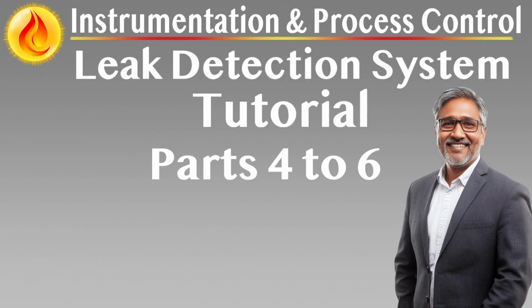These techniques are often used to supplement flow or pressure balance methods, providing an additional layer of detection that focuses on the leak's onset characteristics rather than ongoing mass imbalance. Negative pressure wave detection, commonly referred to as the wave alert technique, is one of the most established methods in this category. When a leak occurs suddenly, especially under pressure, it generates a rapid drop in pressure at the leak site. This pressure drop propagates both upstream and downstream at sonic velocity.